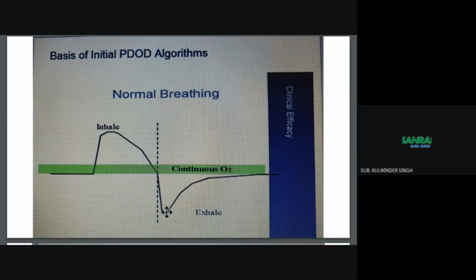This is based on the pulse dose oxygen device algorithms. We can see in the graphics that this is a continuous flow machine, indicated by the green line. The machine is continuously delivering oxygen, but the patient uses oxygen only during the inhale phase, when the patient triggers in pulse mode. During the exhaling phase, the oxygen delivered by the machine is not utilized by the patient, or we can say it is nearly wasted. Now come on to the next slide, please.